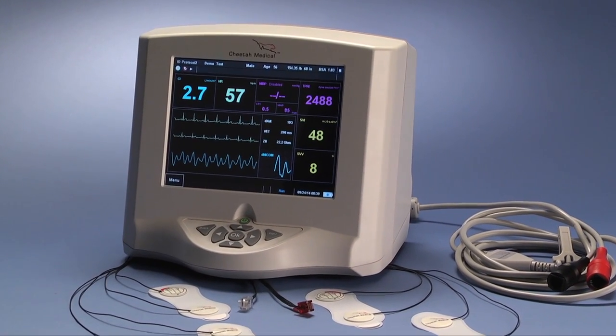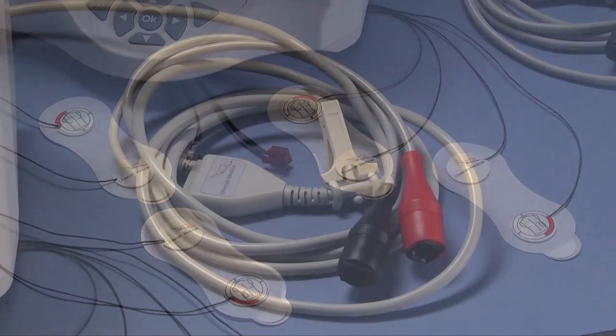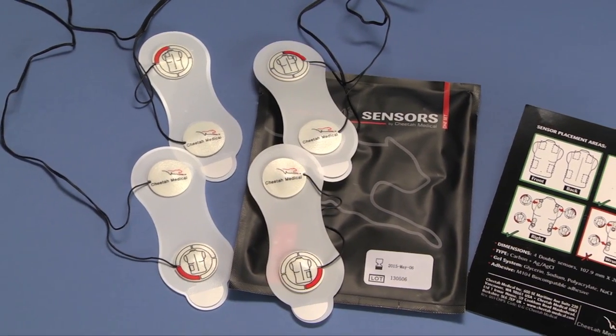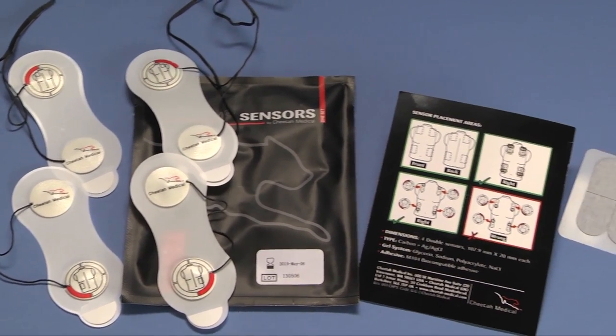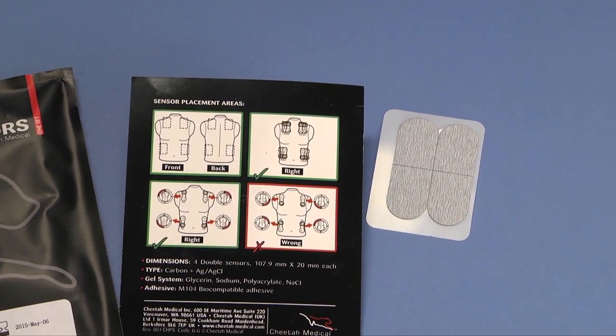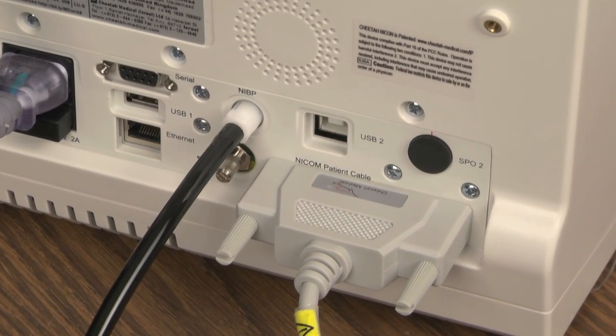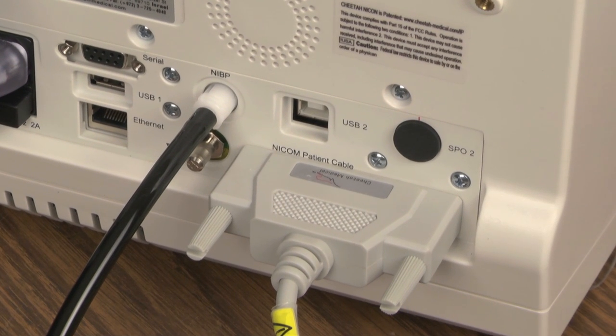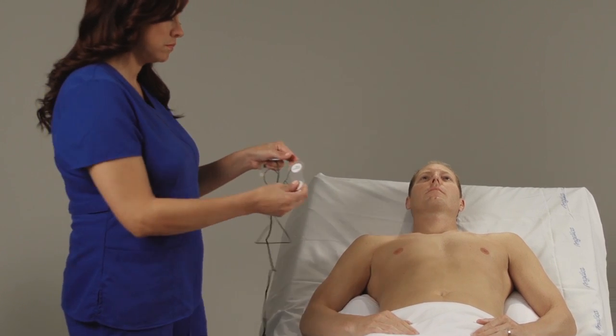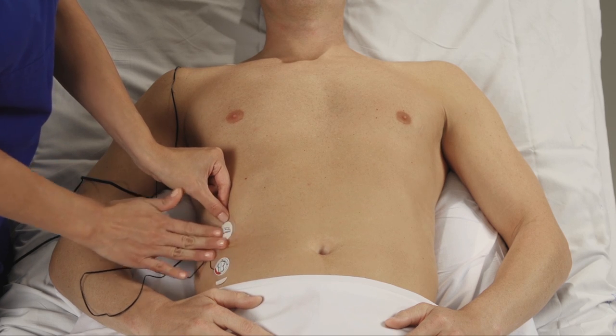The three components of the Cheetah NICOM system are the monitor, sensor, and patient connection cable. Inside the sensor package, you will find two sets of sensors, an instruction card, and an emery board to clean the skin. A single cable connects the left and right sensors to an input at the rear of the monitor. Begin by placing the sensors on the patient, which allows the sensors to start acclimating to the patient as body heat interacts with the gel.